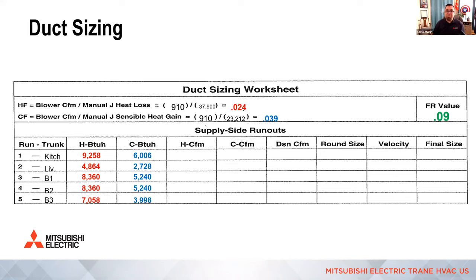And Steve, just to follow up on your question, yeah, 0.09 friction loss comes from the calculated friction rate. So the available static times 100 divided by the equivalent length of the longest run gives us friction loss. If you remember, originally it was 0.15, it was really high. We added a bullhead tee in order to make the friction loss go down in that example.